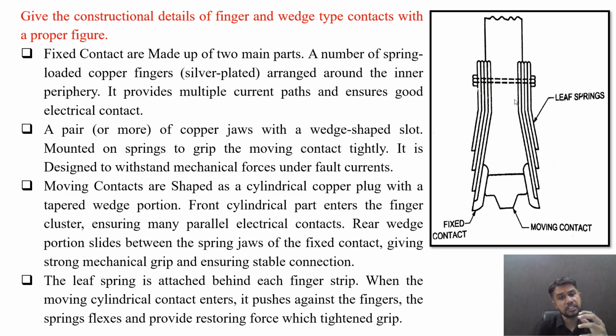It is designed to withstand mechanical forces under fault currents. Moving contacts are shaped as a cylindrical copper plug with a tapered wedge portion. The front cylindrical part enters the finger cluster, ensuring many parallel electrical contacts. The rear wedge portion slides between the spring jaws of the fixed contact, giving strong mechanical grip and ensuring a stable connection.